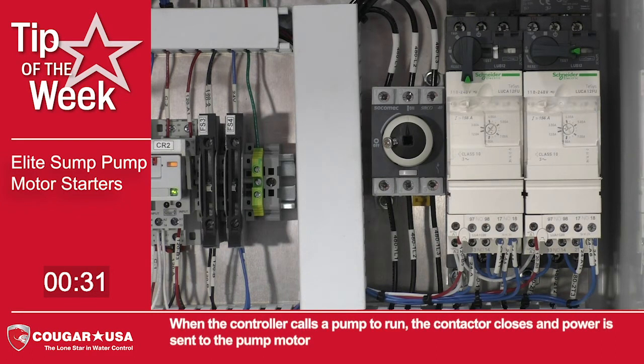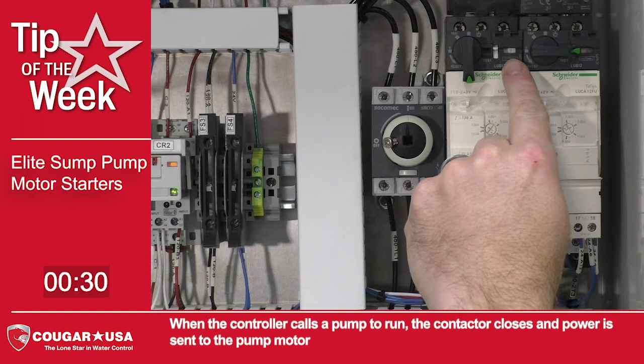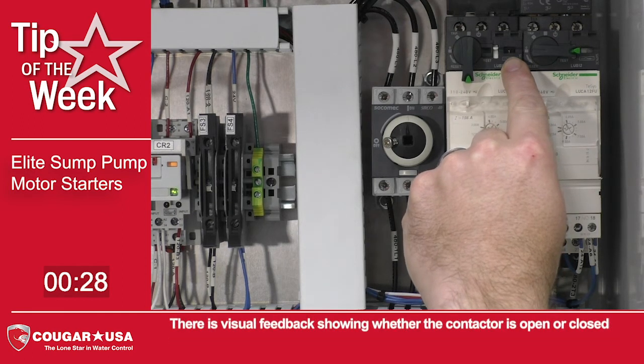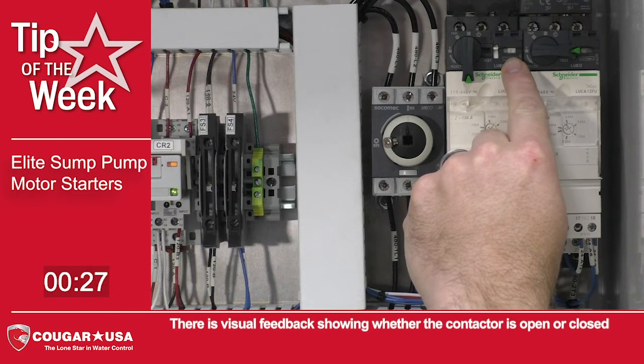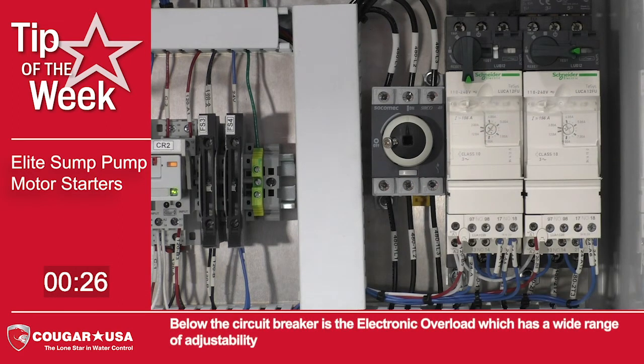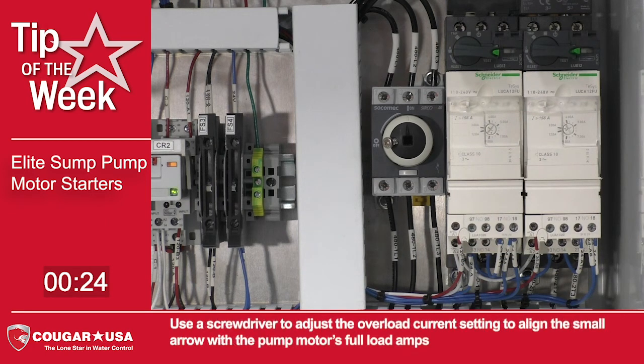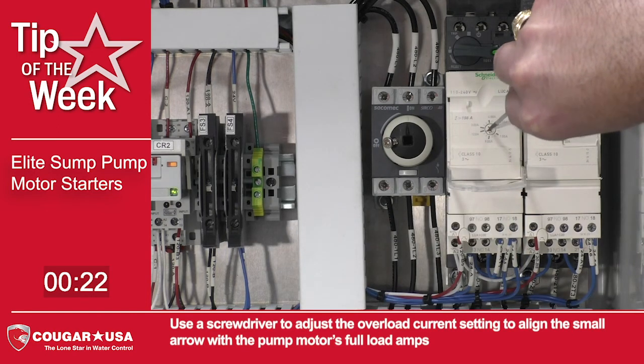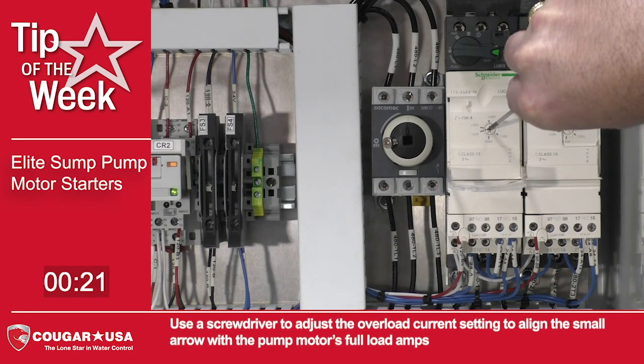When the controller calls a pump to run, the contactor closes and power is sent to the pump motor. There is visual feedback showing whether the contactor is open or closed. Below the circuit breaker is the electronic overload, which has a wide range of adjustability.